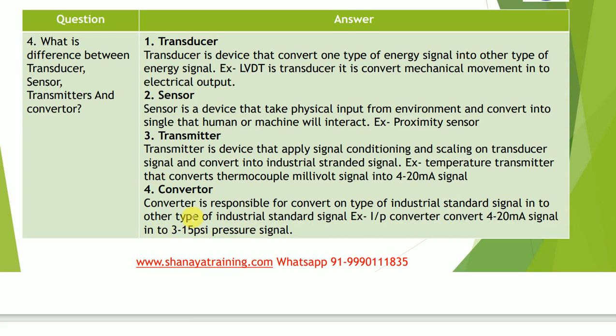A transmitter is a device that applies signal conditioning and scaling on the transducer signal and converts it into an industrial standard signal. An example is a temperature transmitter that converts a thermocouple millivolt signal into 4 to 20 milliamperes. A converter is responsible for converting one type of industrial standard signal into another type of industrial standard signal. An example is an I to P converter, which converts a 4 to 20 milliampere signal into a 3 to 15 psi pressure signal. So this is the fourth question.